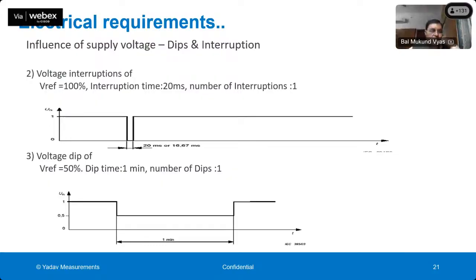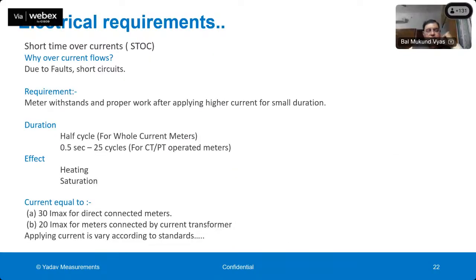There are various types of dips specified in the standard. A dip can be for 1 cycle, which is 20 millisecond, or it can be for 1 minute. So various types of dips are specified, and the meter's accuracy has to be tested before and after that. Another very important test requirement is the short time overcurrent test. This is very important from two points of view. One, the meter should withstand the short circuit, and also it should not cause any fire in the house.